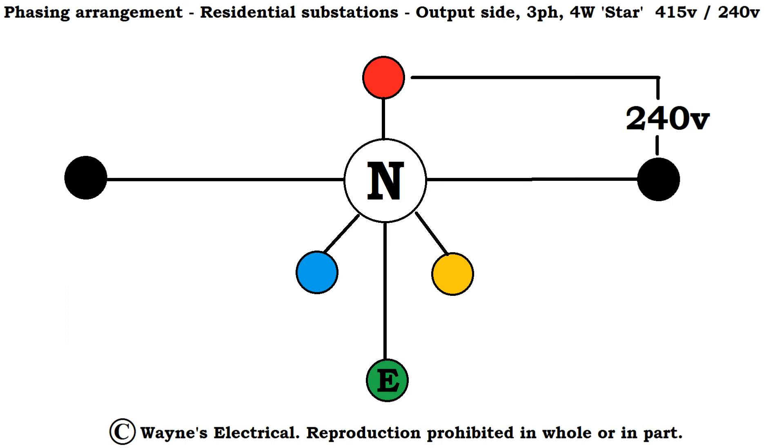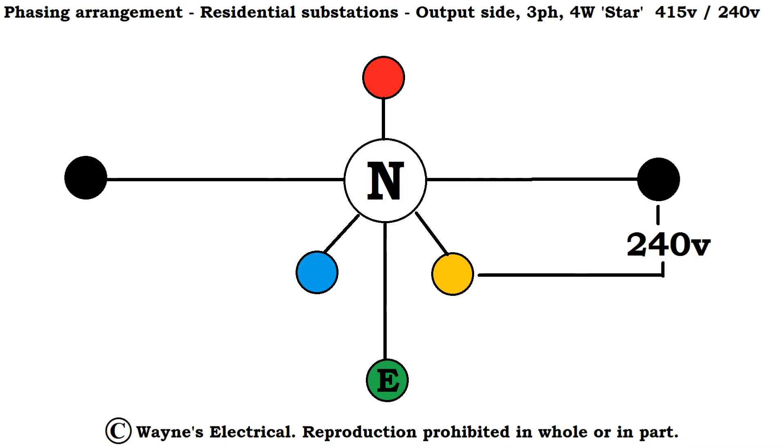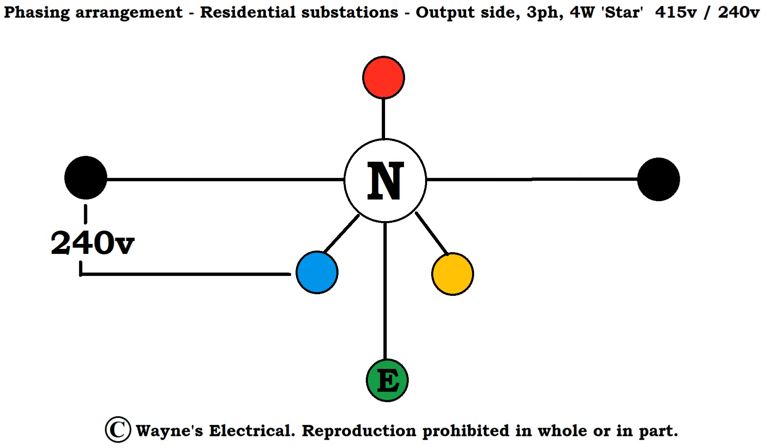But supposing your house is connected on phase yellow and neutral, well it looks a bit like this then. That's right, 240 volts once again. And you know where this is going, if you have this all connected on phase blue to neutral, then it looks a bit like this. There we are, 240 volts once again. And that's what's called a three phase four wire system.